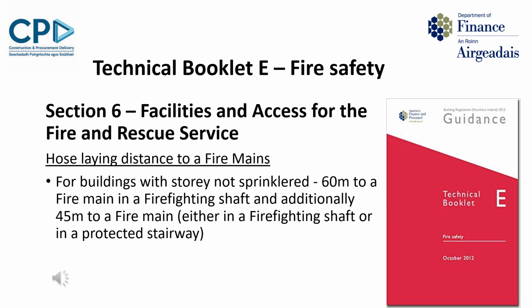However, the amendment means in addition to that, each part of the floor is to be within 45 metres of a fire main. That fire main does not necessarily have to be in a firefighting shaft, but could be in a protected stairway. The 60 metres and 45 metre distances are hose line distances. So if working off plans, direct distances allowable would be 2/3 of these figures, i.e. 40 metres and 30 metres respectively.